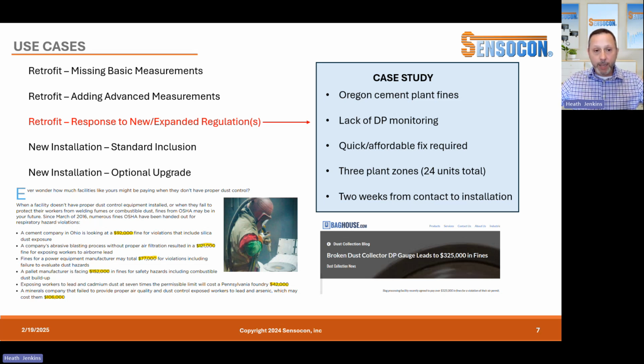They split it into 3 plant zones - it's a fairly large plant with 24 units total, and they wanted to monitor those 3 different zones separately, so only certain sensors are monitored in each zone. That's easy to do by setting up sub-sites within the plant, so employees in zone 1 only see the sensors for zone 1, and so on.